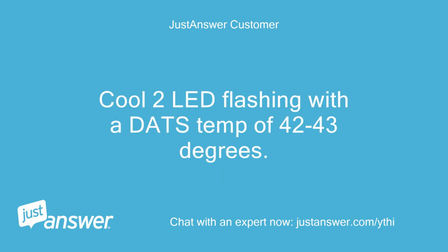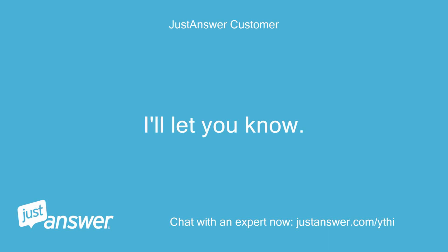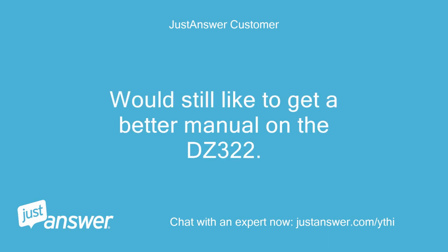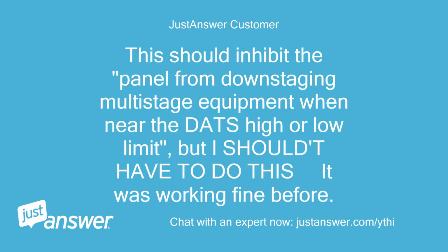Cool 2 LED flashing with a DATS temp of 42 to 43 degrees. I can substitute the 10K and 20K resistors, but I think that'll be fine. I'll let you know. Would still like to get a better manual on the DZ322. I think there's a setting in the advanced config called multi-stage DATS inhibit that would help, change from enabled to disabled. This should inhibit the panel from downstaging multi-stage equipment when near the DATS high or low limit, but I shouldn't have to do this, it was working fine before.